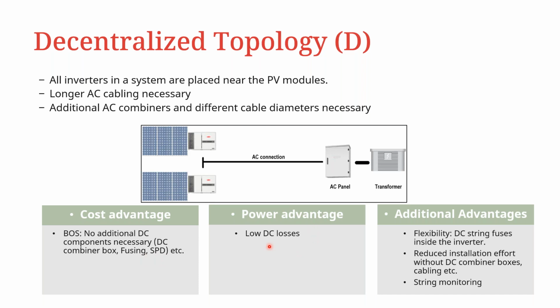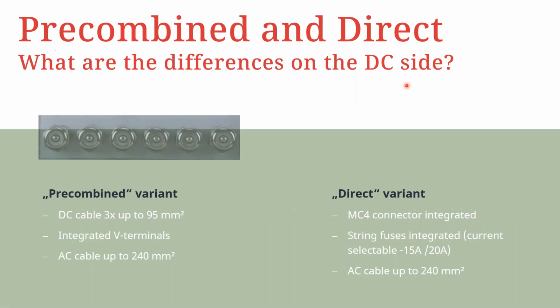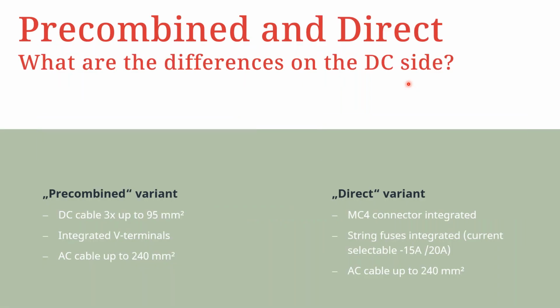The power advantage is the low DC losses, and then if you look at additional advantages that you can get with this kind of topology, you have a lot of flexibility. The DC string fuses are inside the inverter. You have a reduced installation effort, because you do not have to work on the DC combiner boxes, of course. And in addition to that, you can do string monitoring when you have a decentralized topology.